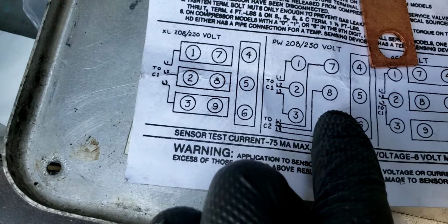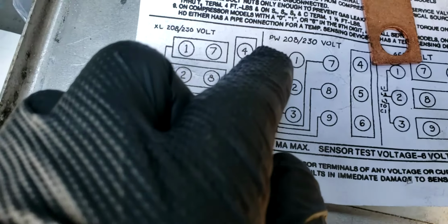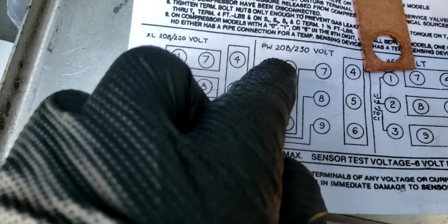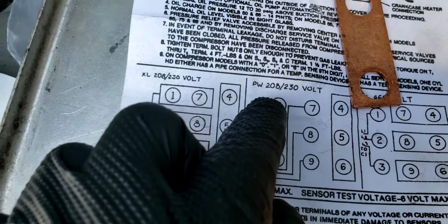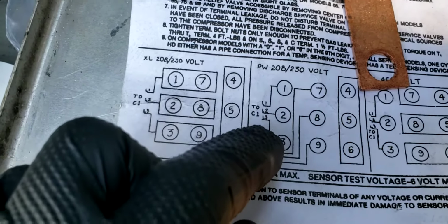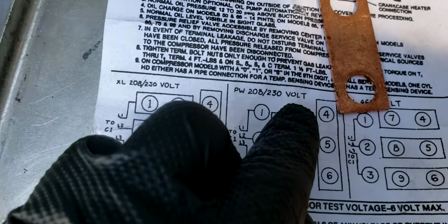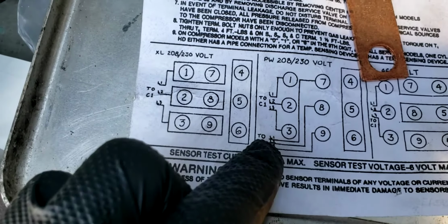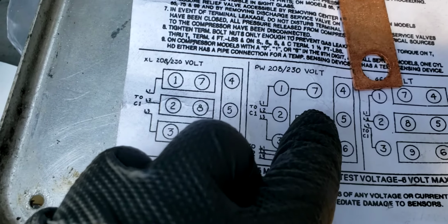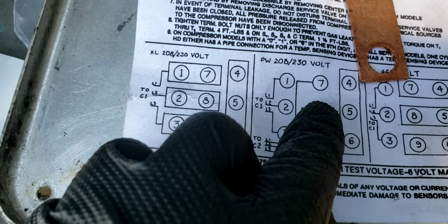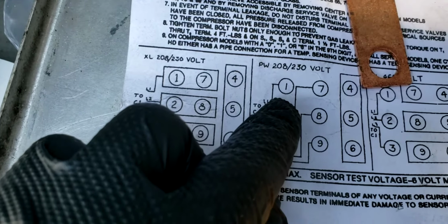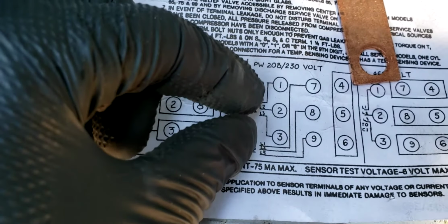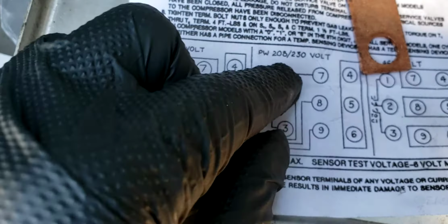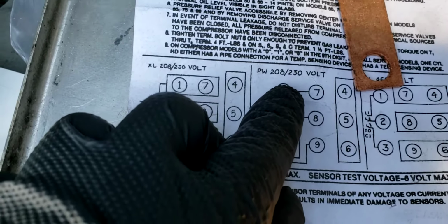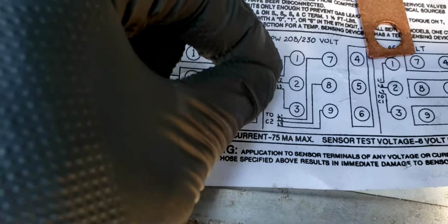Now, you can see that L1 and terminal 1 will share. Also, based on your wiring, L1 down here and terminal 7 should also share, and L2 and terminal 8 share, right? And L2 over here and terminal 2 will be shared. And again, it doesn't have to be in the same order where line 1 goes up here to terminal 1, so long as the input on both of these contactors is in phase.